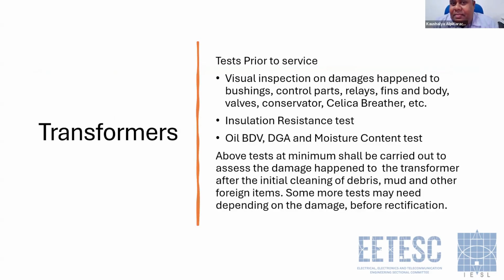Transformers. Testing the transformer prior to the service. First, assess the transformer visually and see whether it is reconditionable, restorable. If so, assess what damage has happened to bushings, control parts, relays, fins and body, valves, conservator, breathers, and all the other stuff.